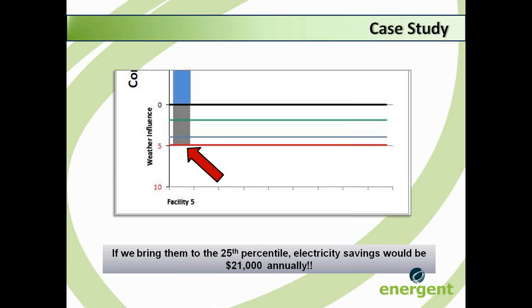If we were able to bring the client down to approximately 5 kilowatt hours per square foot, or the 25th percentile of these Canadian hospitals, it would save the customer $21,000 annually. This means 75% of the hospitals are still operating more efficiently with respect to weather than this hospital, but it still saves them a significant amount of money.